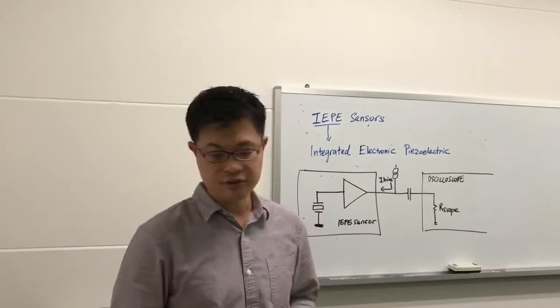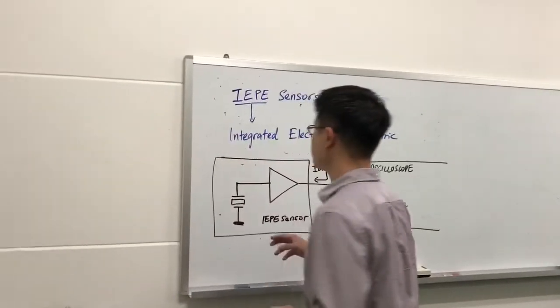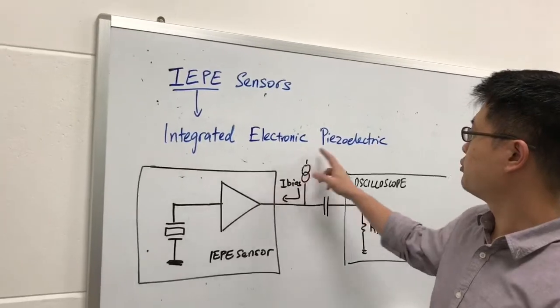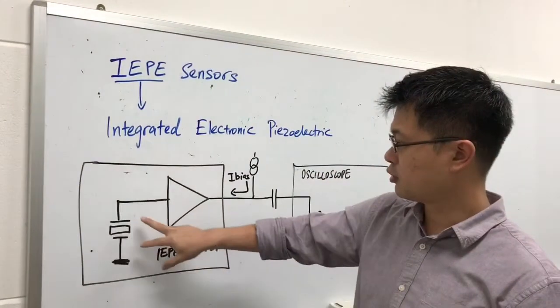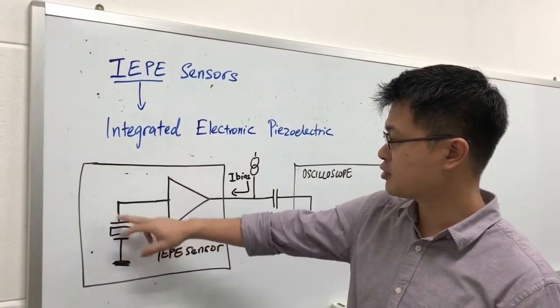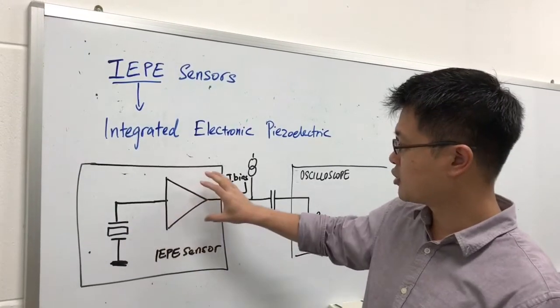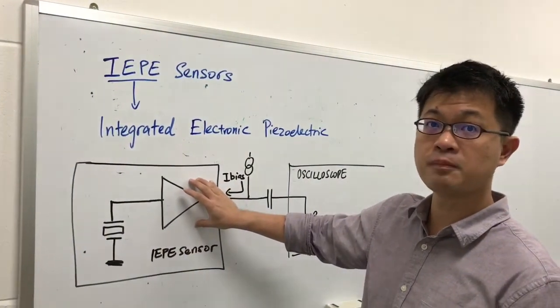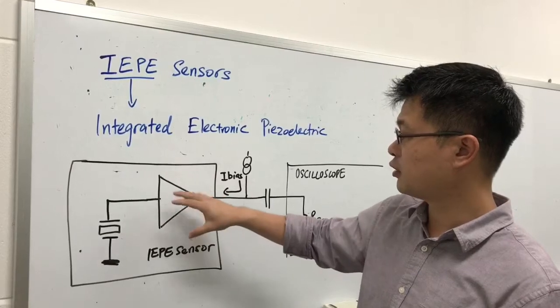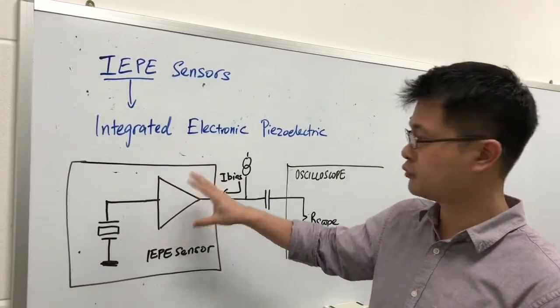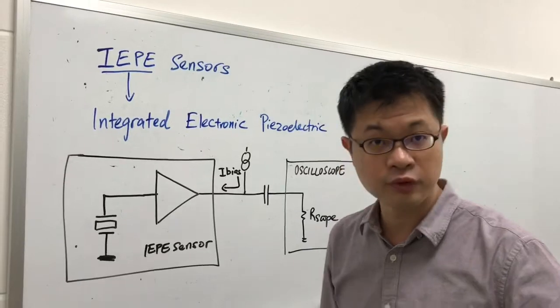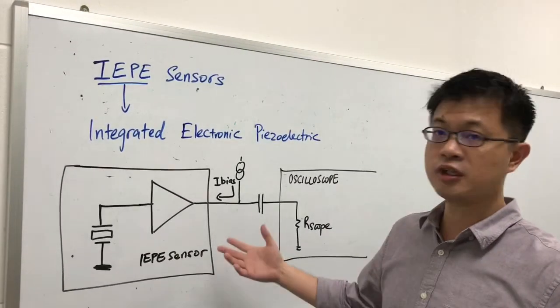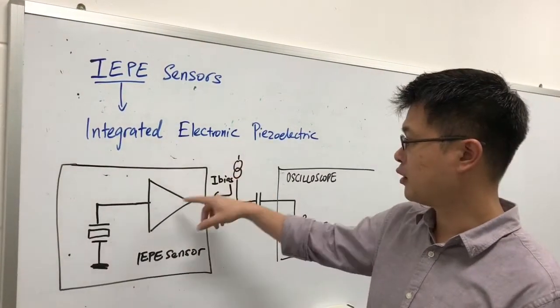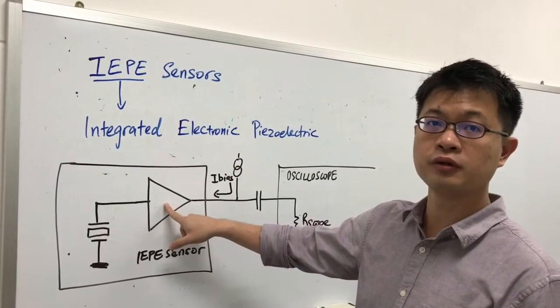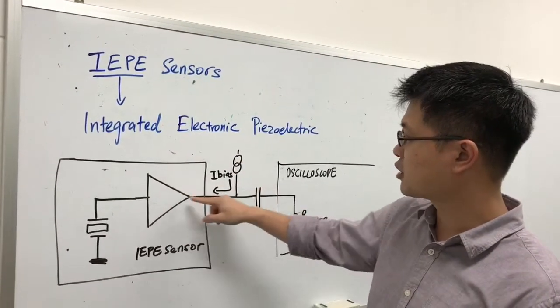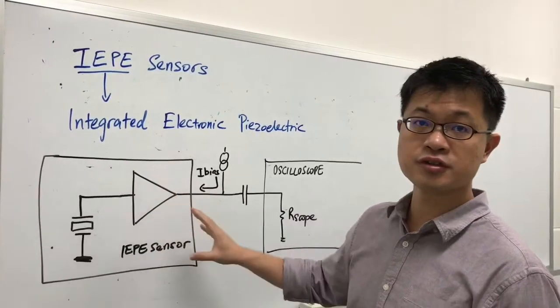Now what are IEPE sensors? IEPE stands for Integrated Electronic Piezoelectric. So in IEPE sensors, you have the sensor, the transducer, and there is an integrated preamplifier. If you connect this kind of sensor directly into a normal scope input, you will not see any signal because this preamp is not powered on.